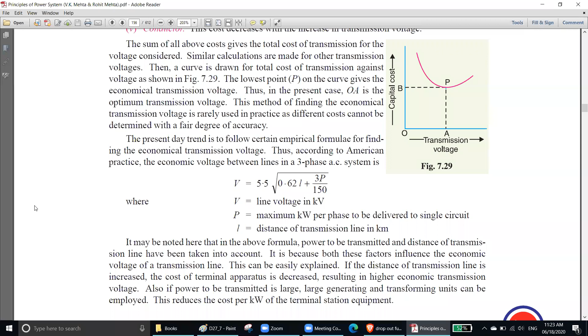Sir, the first point is that if transmission voltage is increasing, the volume of conducting material required is reduced. Yeah, how can that be possible? How can it be possible, right? Why is it reduced? But others are increasing, right? Transformer, because you need a bigger transformer, you need more cost. You need bigger switchgear, that means more cost. You need a bigger lightning arrestor, that is more cost. Insulation, you need more insulation because your voltage is bigger, so you need more cost, right? But how about the conductor, it decreases, right?